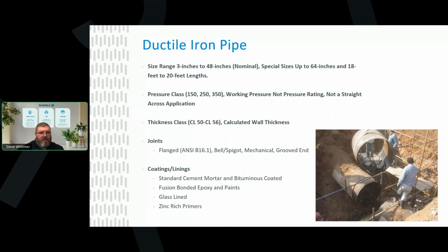So you'll see those other items. Even though it's a pressure class 150, there's actually a lot more that goes into it. For example, when they're considering the thickness of the pipe for a 150 pipe, they'll add in a 2-to-1 safety factor, and then they'll also add in another 100 PSI for the surge that's associated with it, which, surge is a whole nother topic. And funny enough, with everything on this, you can spend a whole another hour on just specialized topics on each one of these.